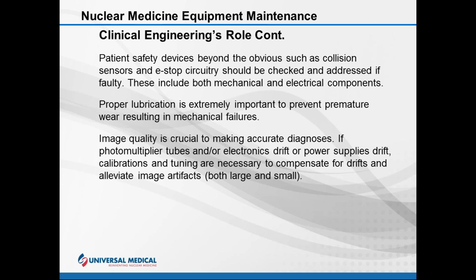And then, of course, most importantly, is the image quality. It's so crucial in making an accurate diagnosis. If the PM tubes or the electronics drift and power supplies drift, the calibration and tuning of these components are very important to alleviate image artifacts that might occur, both large and small. This is important from the technologist's standpoint.